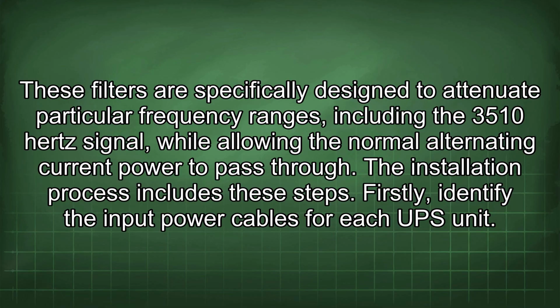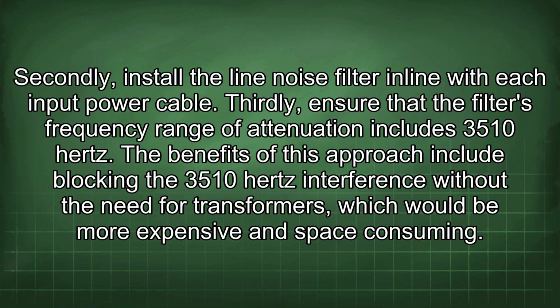The installation process includes these steps. Firstly, identify the input power cables for each UPS unit. Secondly, install the line noise filter in line with each input power cable. Thirdly, ensure that the filter's frequency range of attenuation includes 3,510 Hz.